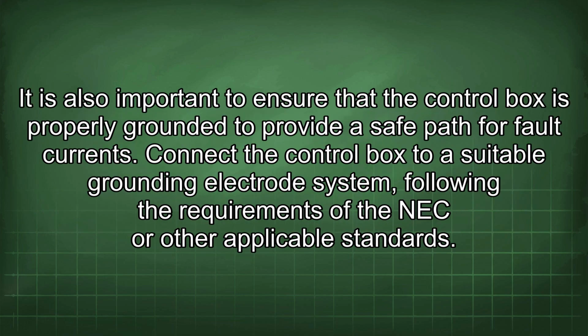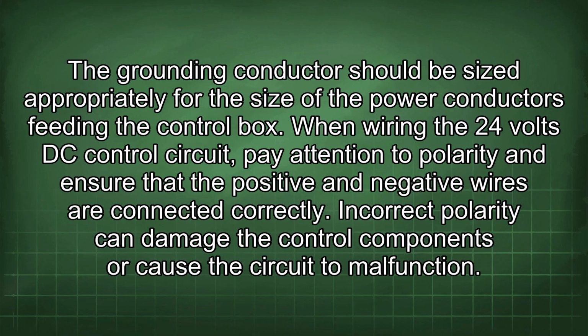It is also important to ensure that the control box is properly grounded to provide a safe path for fault current. Connect the control box to a suitable grounding electrode system, following the requirements of the NEC or other applicable standards. The grounding conductor should be sized appropriately for the size of the power conductors feeding the control box.